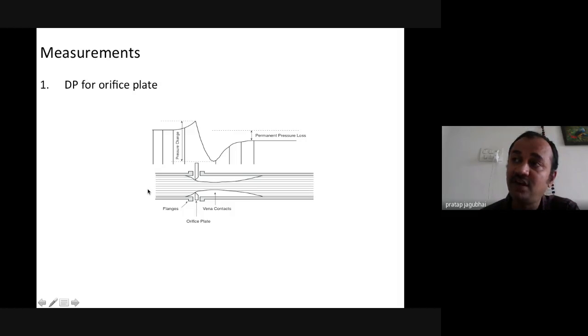And this is very widely used to measure superheated steam basically, and water flow also, and in some cases gaseous flow also, where the gas is an inert gas and it's not a clean gas, and very difficult to measure and directly take inside the very fine instruments, frequency measurement instruments. So in that application, the DP type measurement is very widely applicable.